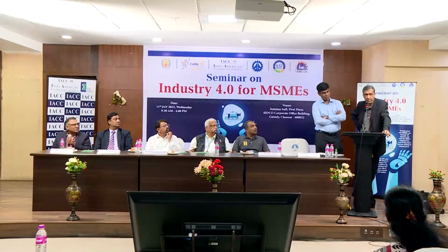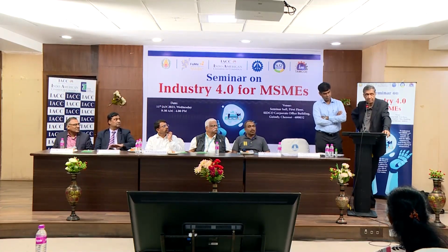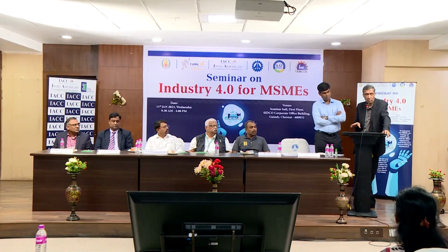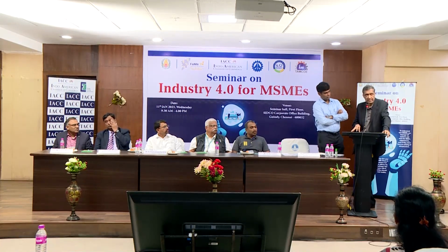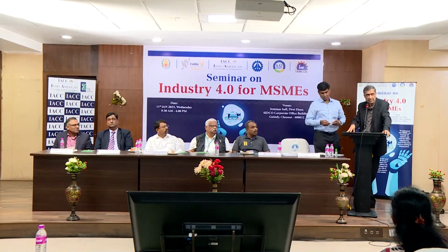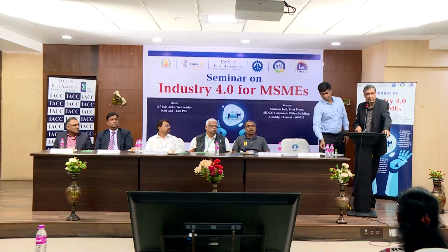Again, this is a generic question. I just want to add one thing to that. Yes, you can integrate with SAP, but that's why one of the things I talked about was architecture. If you have a very easy contact between your operational system and your ERP, it makes it easy for a hacker who comes into the OT system to hack into your SAP system, or anybody who hacks into your domain system to hack into your PLCs on the shop floor.